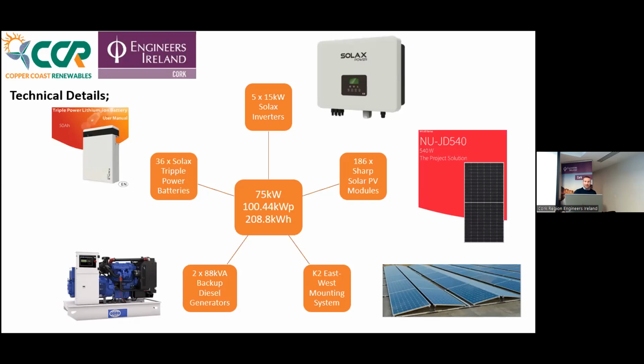We actually have two 88 kVA diesel generators and a 33 kVA diesel generator on site. They've had them for years. So what we did is we recommissioned the diesel generators. We've got a dual auto transfer switch. The way everything is set up, and we'll run through a single line drawing in a second, is the site runs on solar and batteries as much as possible. If the solar and batteries can't provide the load, the diesel generator kicks in. If the diesel generator were ever to fail, there's another automatic transfer switch onto the second diesel generator.